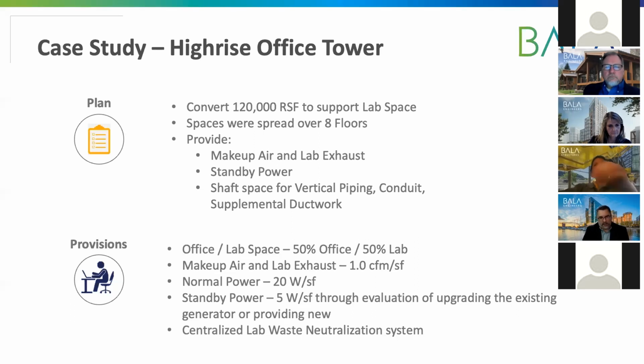And essentially, that's being spread out over 8 floors. And as I mentioned earlier about the chemical usage, the owner in this case considered that when they were picking the floors they were going to convert. So we end up going with lower floors. But essentially, we're going to span that gap I was talking about at the 4th floor where the code kicks in and really restricts your stored volume. So in this case, we're looking at floors 2 through 9. So we'll have a little bit easier going on the lower floors, but the upper floors, they'll have limitations.